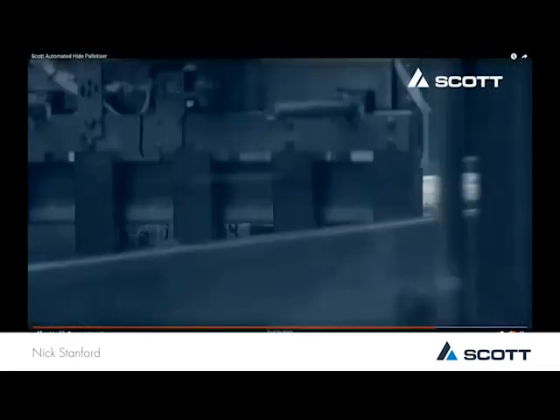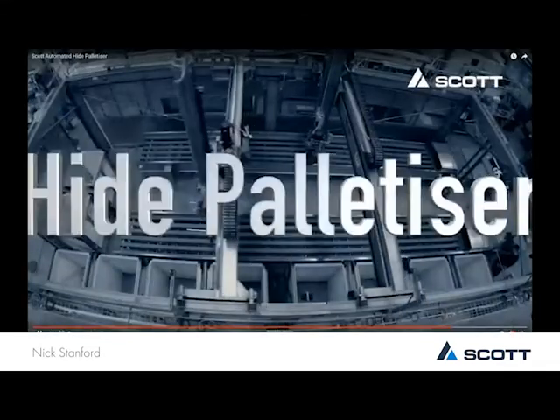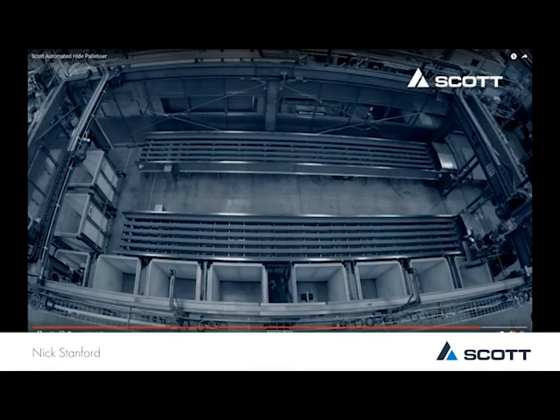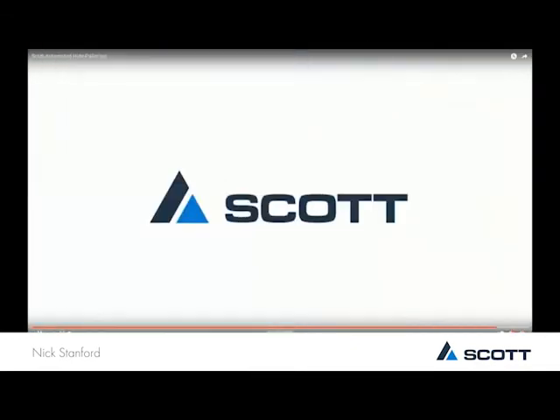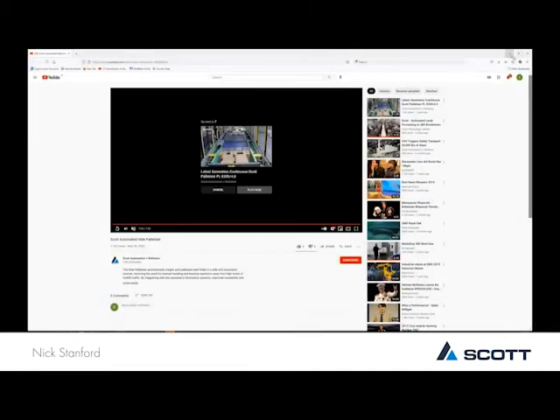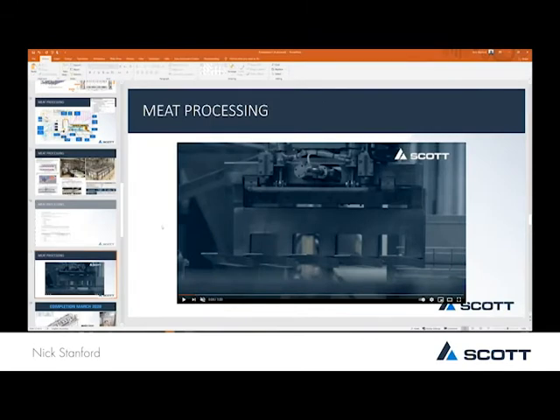The biggest challenge in the project is the high salt content of the product, so everything is designed with stainless steel grade 316 marine grade to make sure it can handle that salt content. That applied to a lot of components in touch with the product. The other challenge was the fat content and the slippery nature of the product, to make sure we are not dropping it while we are handling it from A to B.